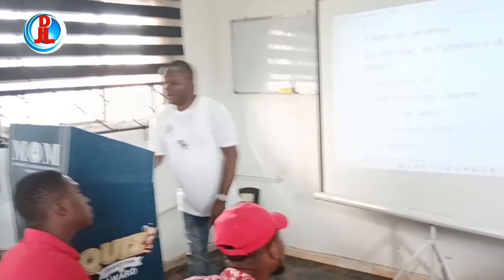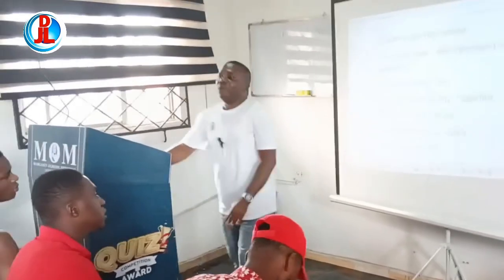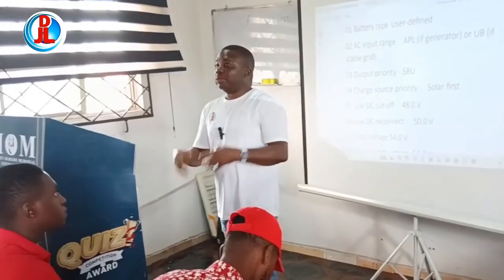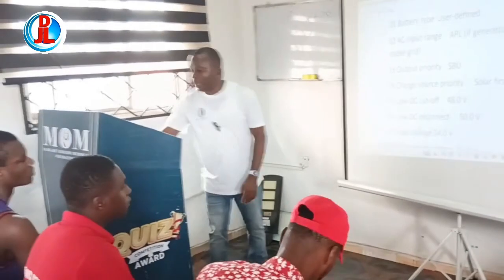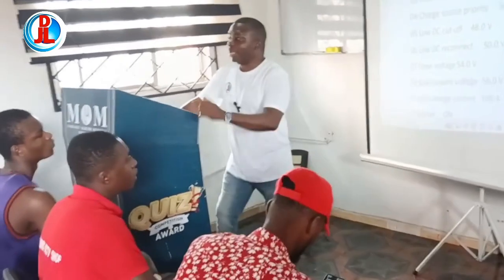Low disconnect 48. Low DC reconnect 50. So when the thing gets to 48, it shuts down. Then by the time it starts charging, when it gets to 50, it reconnects back. Float voltage 54. Bulk voltage 56.